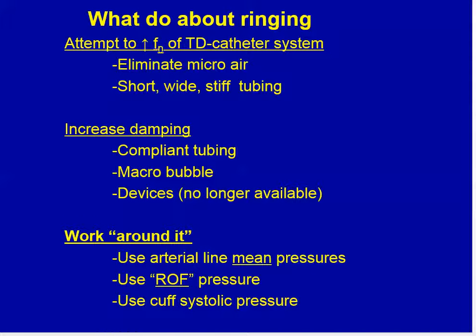So what do we do about ringing? You can attempt to improve the natural frequency of the transducer system by eliminating any micro air, shortening the tubing, and getting rid of stopcocks. You could artificially increase damping by adding a section of compliant tubing or a macro bubble. Or you can work around it by using the arterial line mean pressure, which is unaffected by ringing, by using the return of flow pressure to measure systolic pressure, or simply using the cuff to measure systolic pressure.